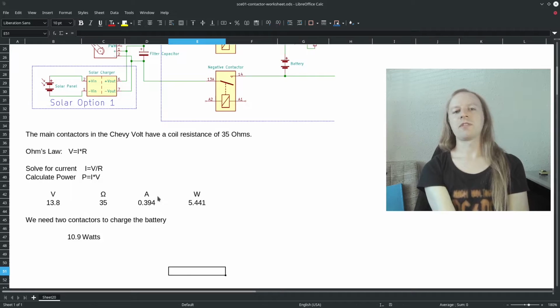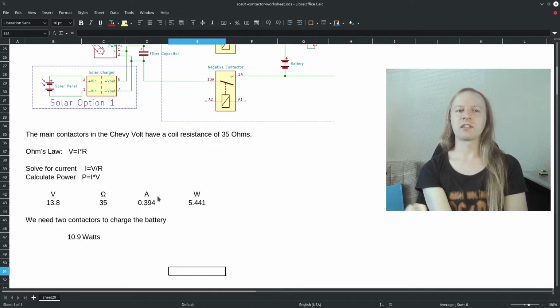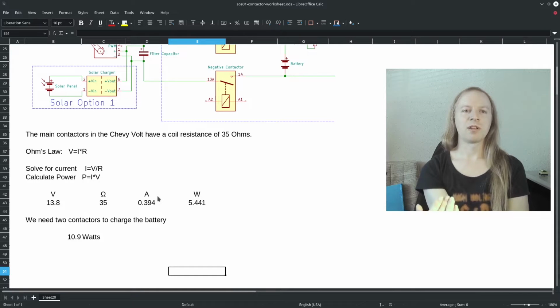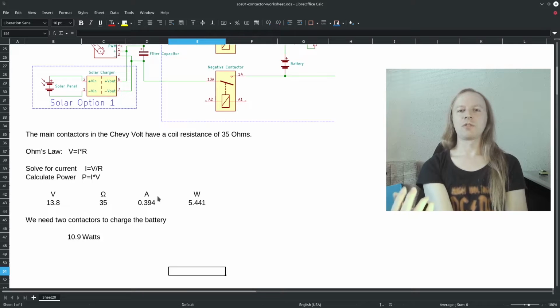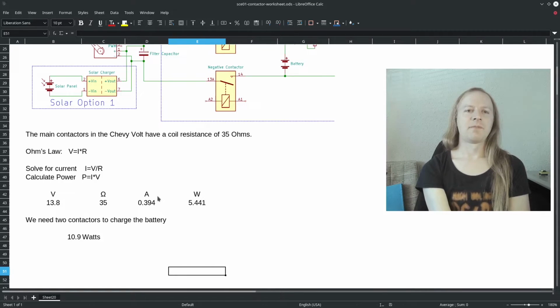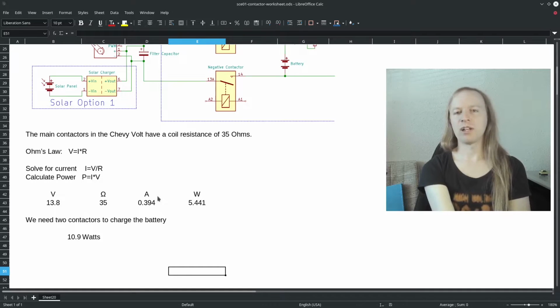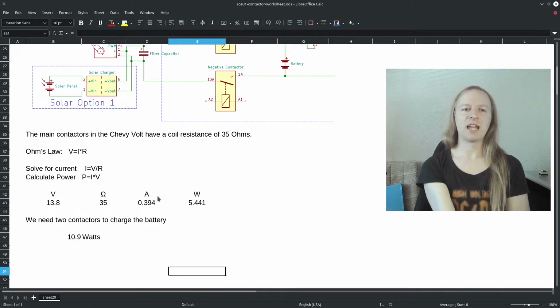We found that the contactors for the Chevy Volt have a coil resistance of 35 ohms. Given the voltage the car operates at, the coils need 12 volts nominal to operate. If we assume 13.8 volts actual voltage and 35 ohms, using Ohm's law we calculate almost 0.4 amps. Then we calculate power, which is amps times volts, and find it's almost 5.5 watts to run one contactor.